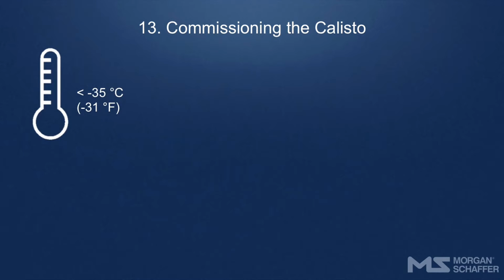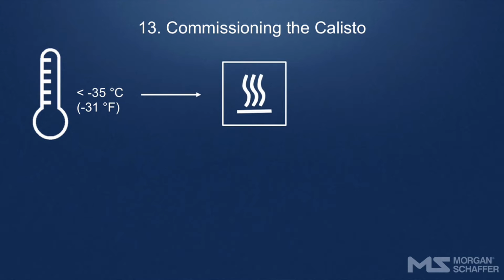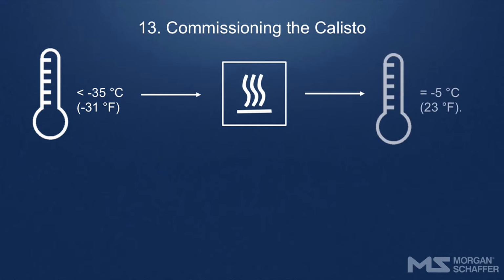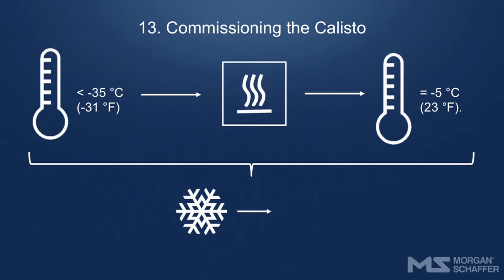If the monitor temperature falls below -35 degrees Celsius or -31 Fahrenheit at startup, the monitor will enter a preheating mode where only the internal heating elements of the Calisto will be in operation. The unit's onboard computer will start up once the Calisto's internal temperature reaches -5 Celsius or 23 degrees Fahrenheit. In extremely cold weather, it could take several minutes or even several hours to reach this temperature. For more details, please refer to the installation and operation manual.